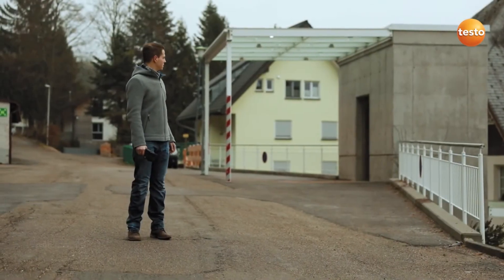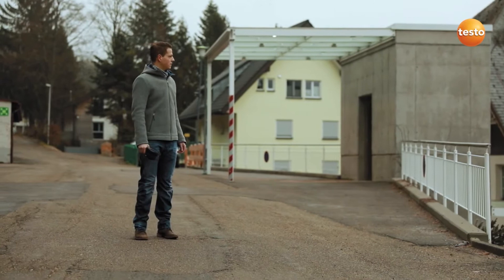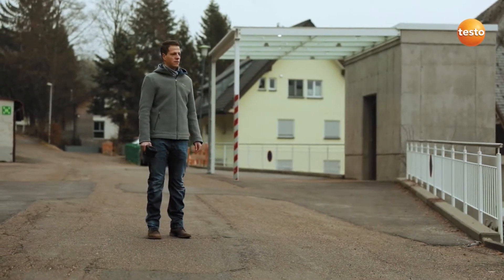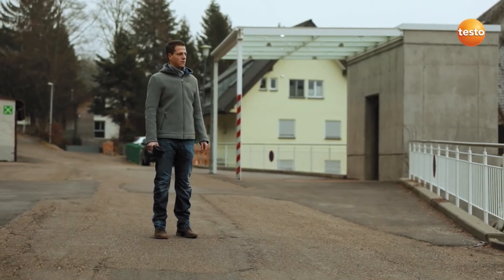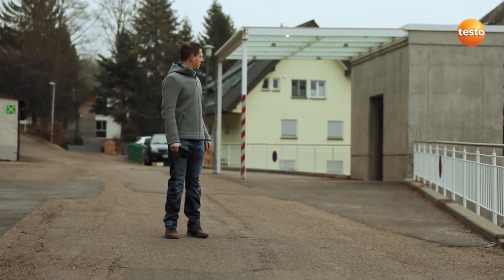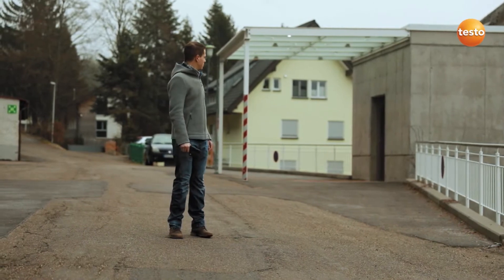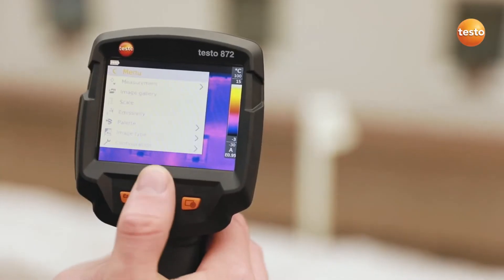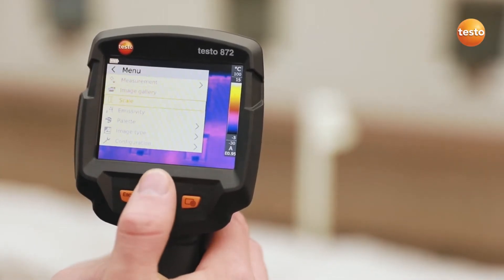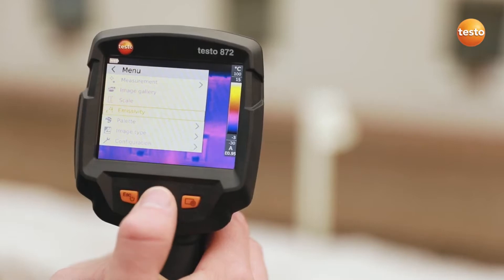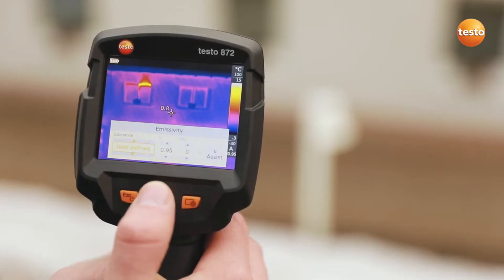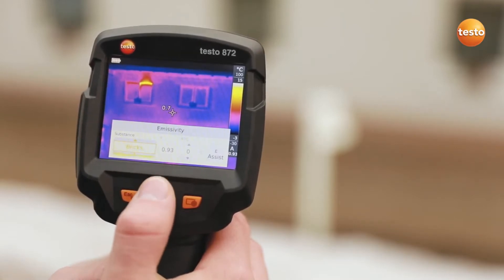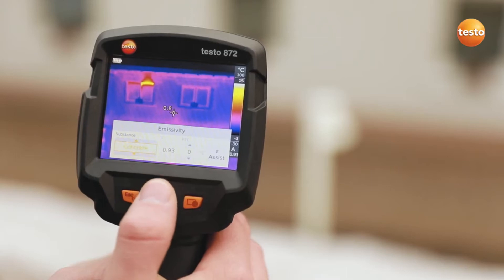Today we're going to show you how you can use the Thermal Imager Testo 872 to detect faults on and in buildings quickly and unambiguously. First of all, in addition to the ambient temperature, you have to set the emissivity in the imager. Thanks to the stored table, this is very easy to do.